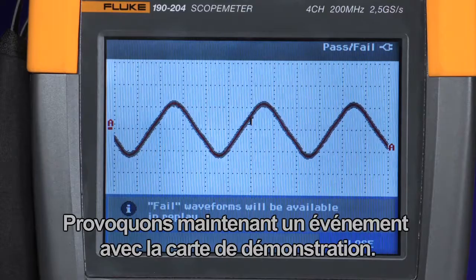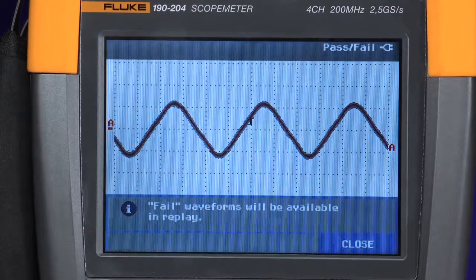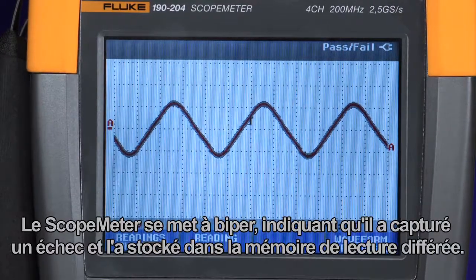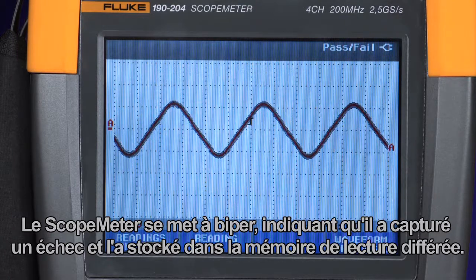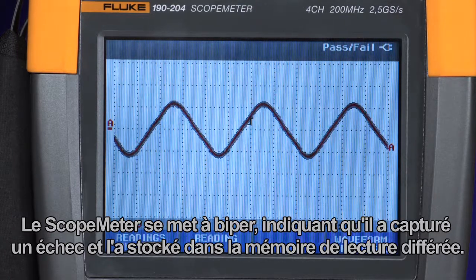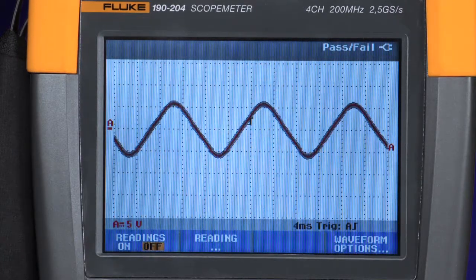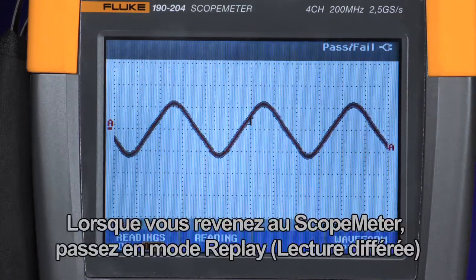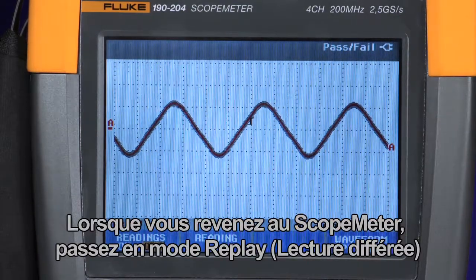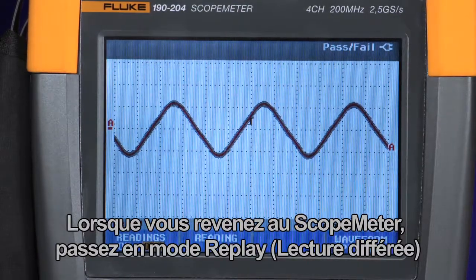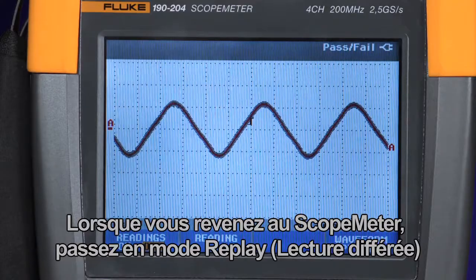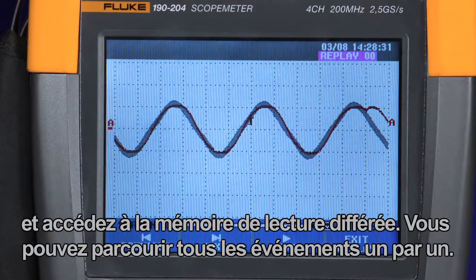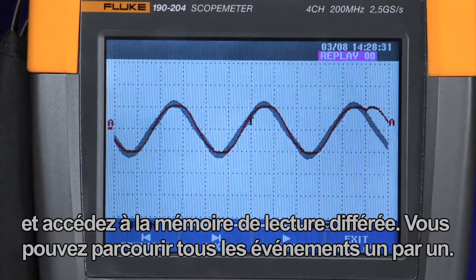Now let's cause an event using the demonstration board. The scope meter will beep indicating that it has captured a fail and stored it in the replay memory. When you return to the scope meter, simply go to the replay mode, access the replay memory, and you can scroll through each of the events one by one.